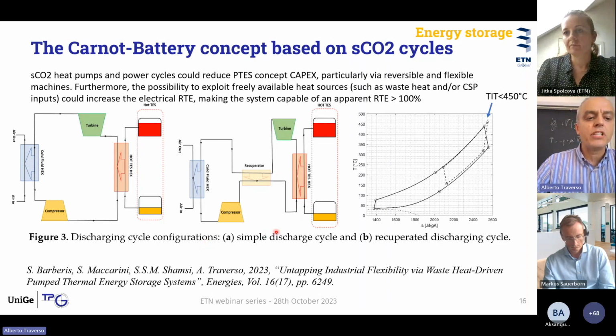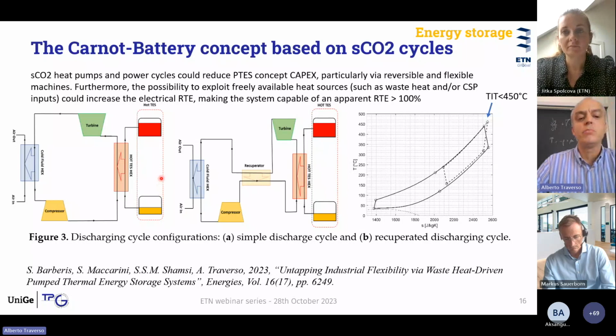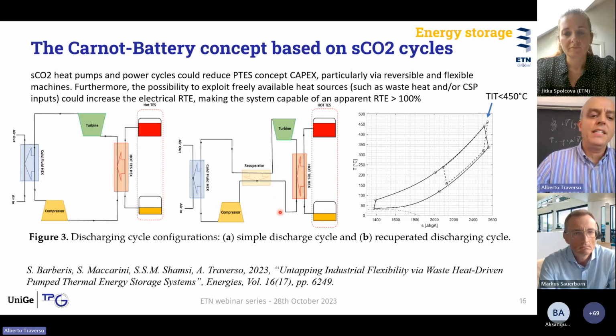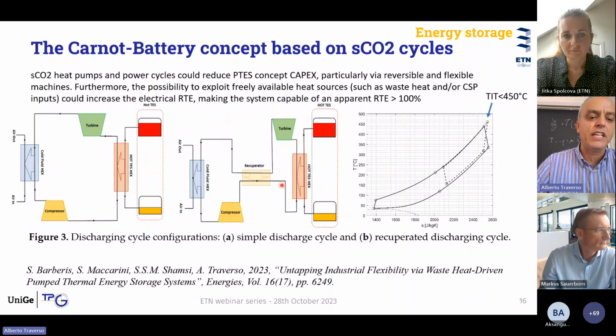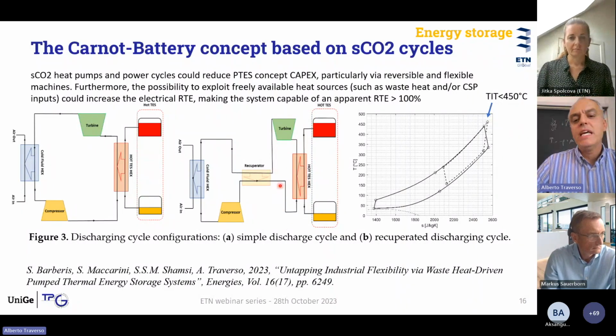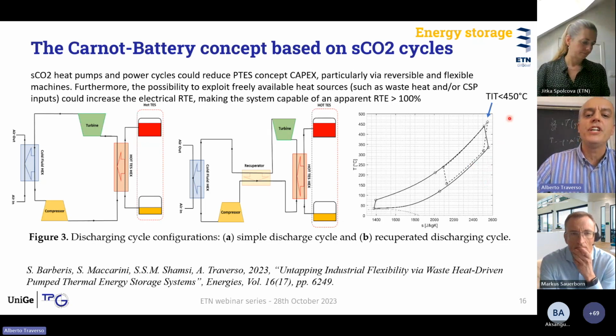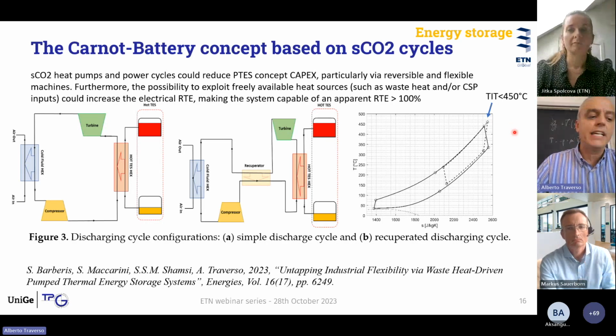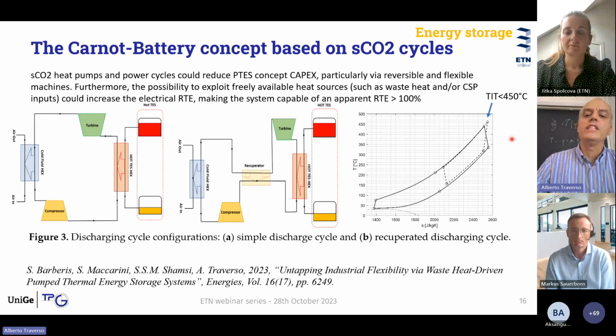If we look at the layouts reported here, for instance, we are showing two different layouts for the discharge phase, where on the left is a simple supercritical cycle, and on the right we have a simple recuperative supercritical cycle. In this case, the charging and discharging cycles interact in order to define the specification of turbomachinery, in particular if reversible turbomachinery is to be developed. But if we look at the TS diagram of the two cycles, one charging phase, the other discharging phase, and we look especially at the expander inlet condition, we see that again, even for the Carnot battery, we are talking about inlet conditions which are similar to the waste heat recovery case. The optimal TIT is a little bit higher, 450 degrees C, during the charging phase, but they are quite similar to that case.